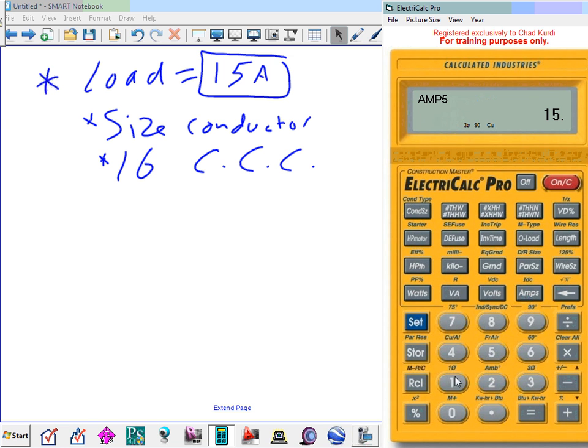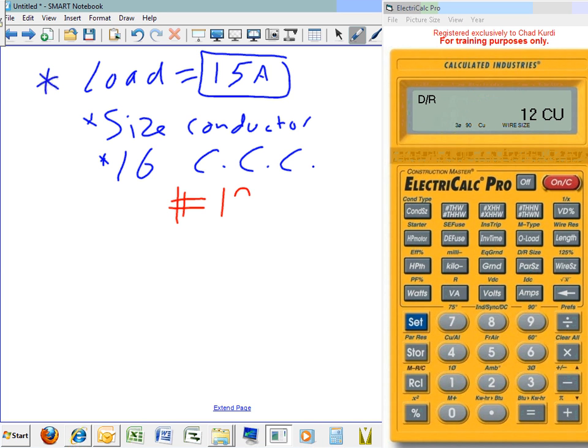The second thing I need to tell it is how many current-carrying conductors I actually have: 16. Now you hit the 16 and then you're going to hit set and size conductor. And your conductor is going to be what? Number 12, as it should be, right? Number 12, based on the 15 amps. So my conductor based on this calculation, as we proved, is number 12 AWG.